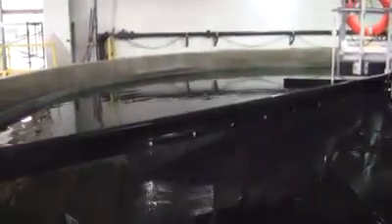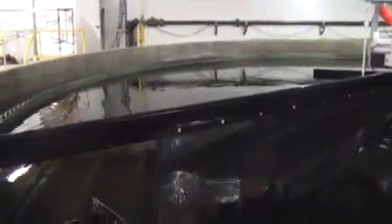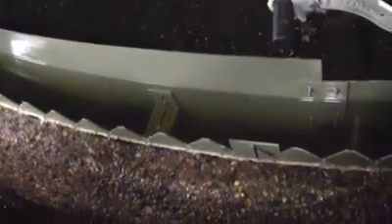These are our secondary clarifiers, and this is where we separate the bugs from the treated wastewater. Now it's clear water. The bugs go to the bottom of this tank and they're removed, and they're either wasted out of the system or returned back to the front of the activated process. The clear water comes to the top, the bugs go to the bottom. The water going over these outside weirs is the treated wastewater now, and you can see it's substantially cleaner.